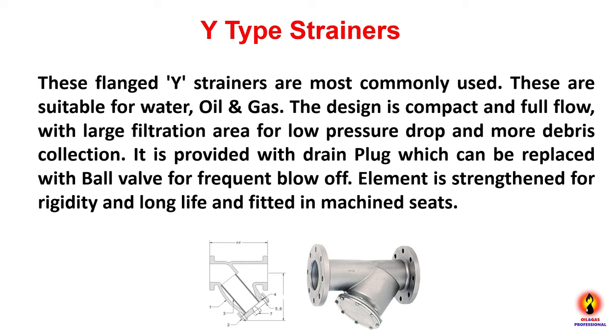Flanged Y-type strainers are most commonly used and are suitable for water, oil, and gas. The design is compact and full flow with a large filtration area for low pressure drop and more debris collection. It is provided with a drain plug which can be replaced with a ball valve for frequent blow-off. The element is strengthened for rigidity, long life, and fitted in a machined seat.